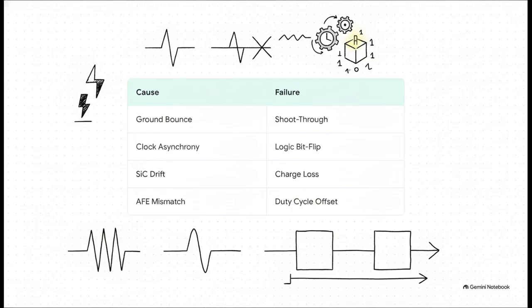So, how do these microscopic phenomena actually ruin our day? Well, that high dV/dt ground bounce makes the ground potential jump violently, causing a 0-volt signal to look high, which triggers a microsecond cross shoot-through, basically firing the upper and lower bridges at the same time. Not good. GTM asynchrony flips logic bits, creating dangerous narrow pulses. SiC thermal drift slows down gate charging, entirely distorting your duty cycle. And that AFE leakage? It tricks the brain into thinking it's outputting one voltage when it's actually doing another, causing severe PWM duty cycle offsets.